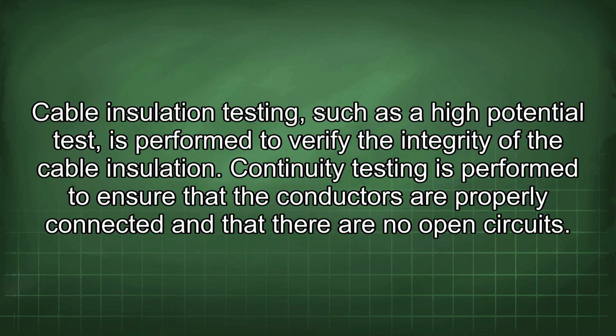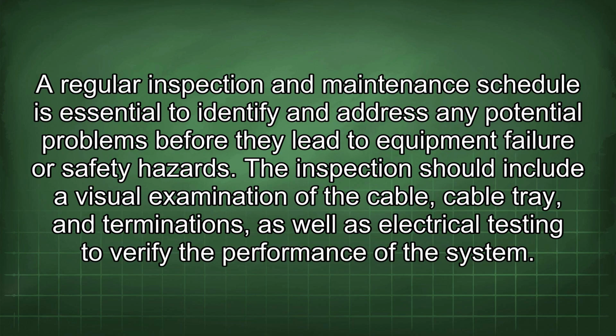Cable insulation testing, such as a high potential test, is performed to verify the integrity of the cable insulation. Continuity testing is performed to ensure that the conductors are properly connected and that there are no open circuits. A regular inspection and maintenance schedule is essential to identify and address any potential problems before they lead to equipment failure or safety hazards. The inspection should include a visual examination of the cable, cable tray, and terminations, as well as electrical testing to verify the performance of the system.